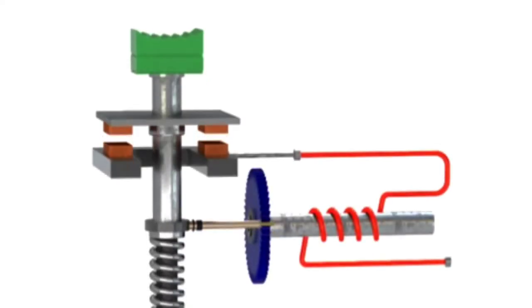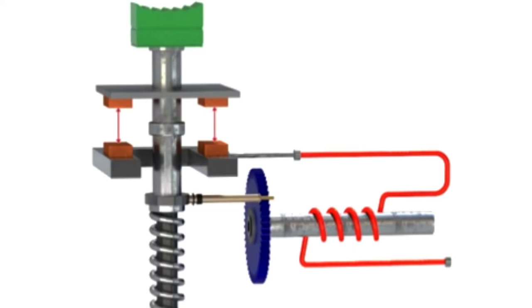This pawl is connected to a spring-loaded contact fixture, such that when the pawl trips, the contacts automatically open and stop the current flowing to the motor starter.